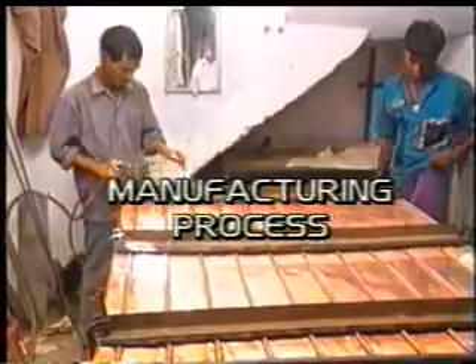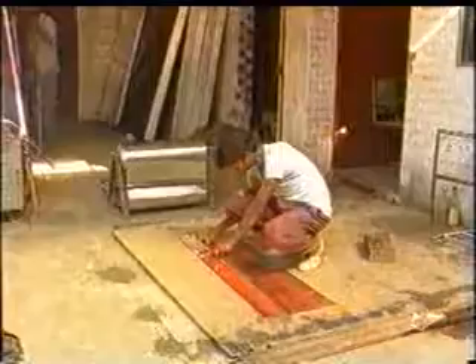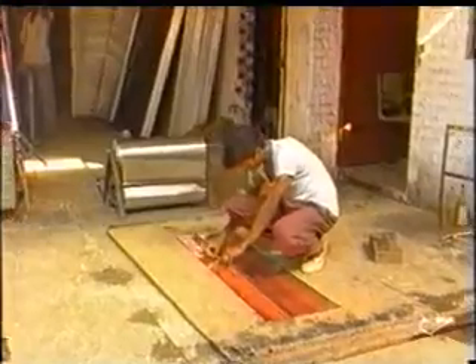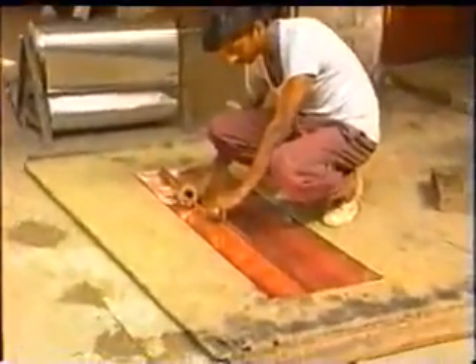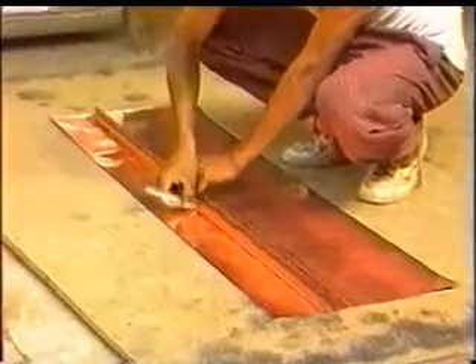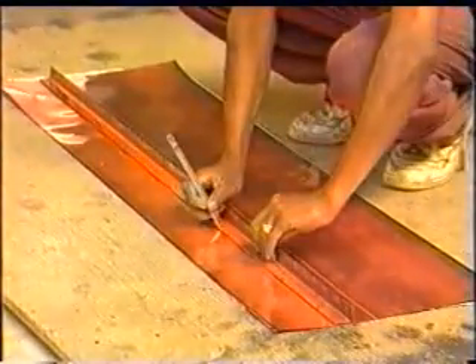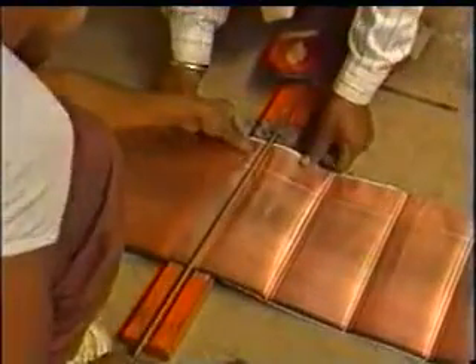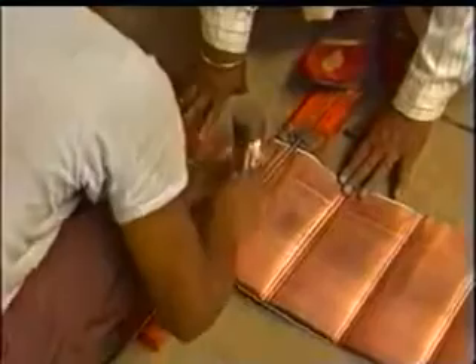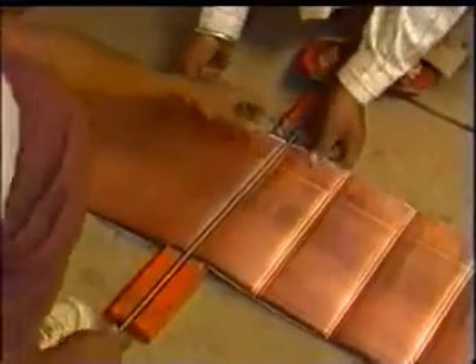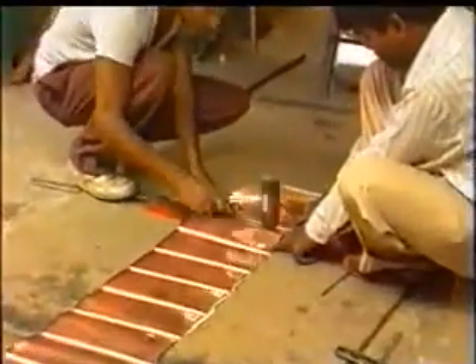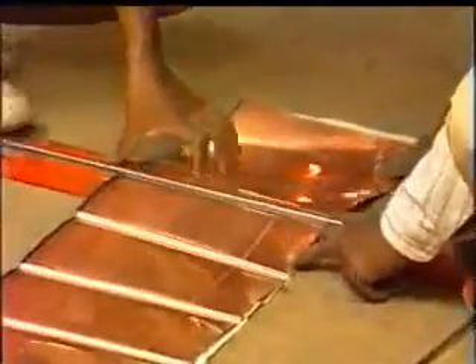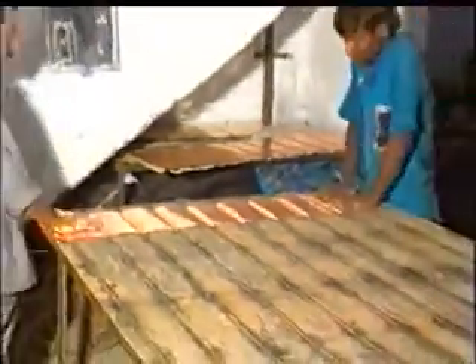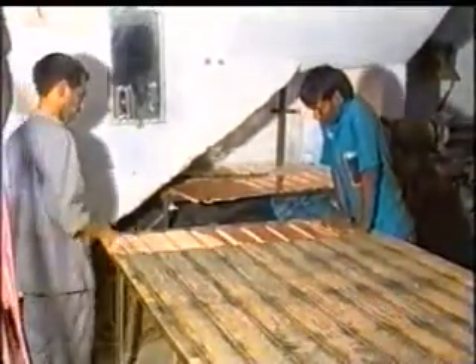Let us have a glance at the manufacturing process of the collector. In the beginning, a very thin copper sheet which is blackened with selective coating, is measured, marked, and cut as per the required size. This is followed with grooving. The grooves are made for fixing of riser tubes. The grooved sheets are assembled one by one on the mount so as to make the standard size of the absorber.